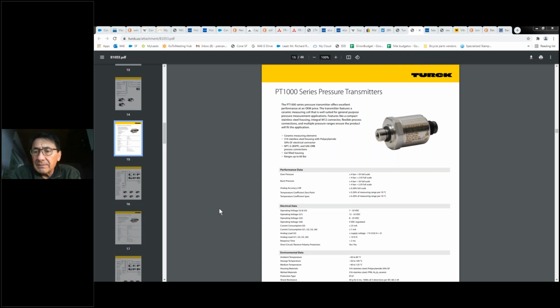And I'm going to say that I don't recommend the field wiring practice right off the bat, but I do recommend using pre-wired over-molded cables that basically screw in with a seal. It is an easy operation, it's relatively hard to make a mistake, and the over-molded connection on the sensor head itself is secure for years. So the sensor, type 316. Stay away from the type 304 stainless stuff because that's basically the less expensive version, and it doesn't hold up very well in terms of corrosion. Type 316 is a superior alloy. And then an over-molded, easy to install connection, no field wiring.